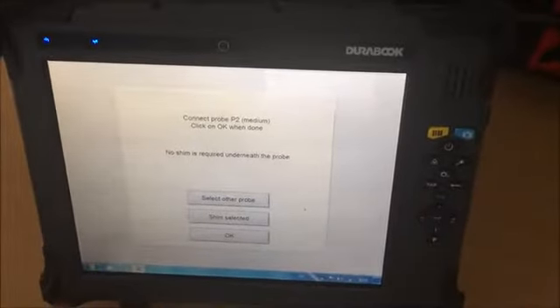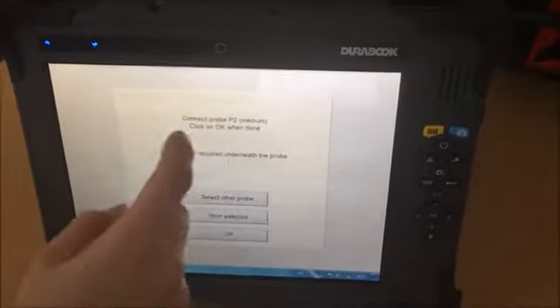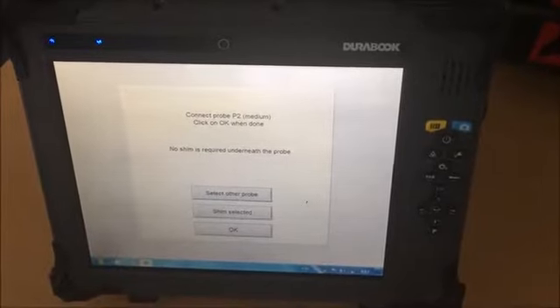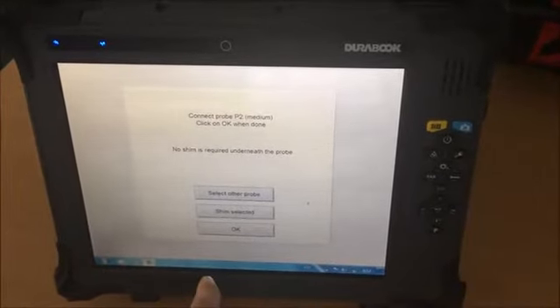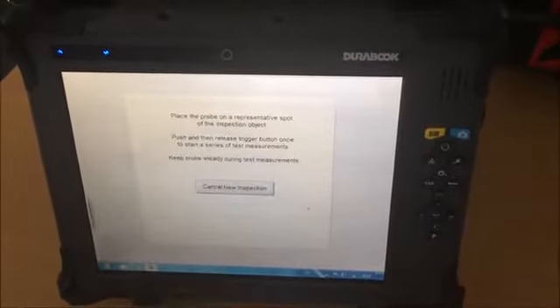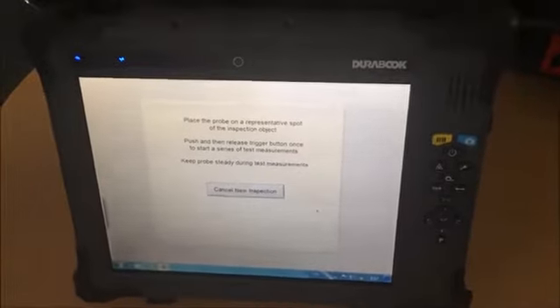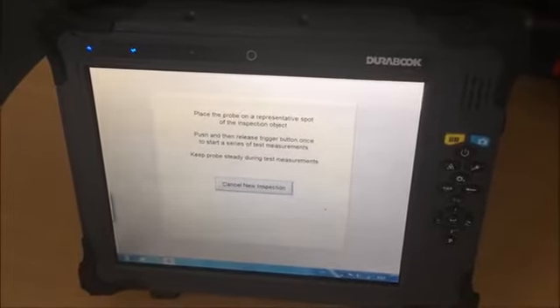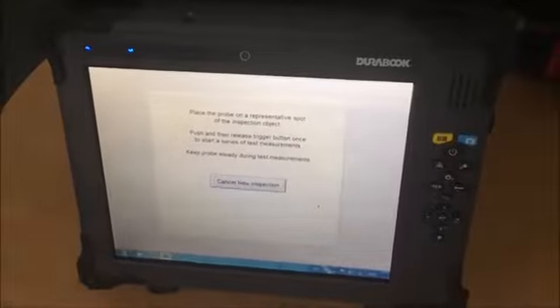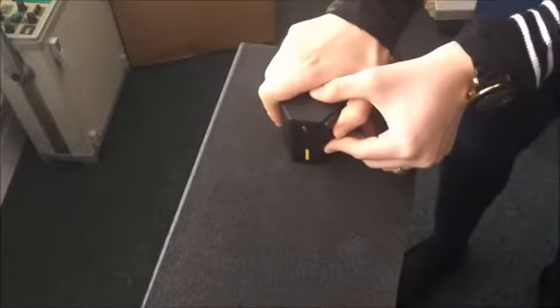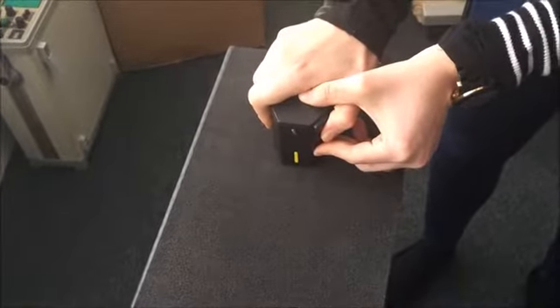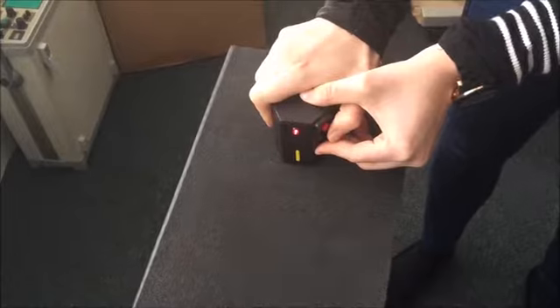Okay, now the system is telling us to connect the probe P2, which is the medium one. It's already connected. We can click OK. And now it's saying to place the probe on a representative spot on the inspection object. Place the probe. It's important to keep the probe still. And we push the red button.